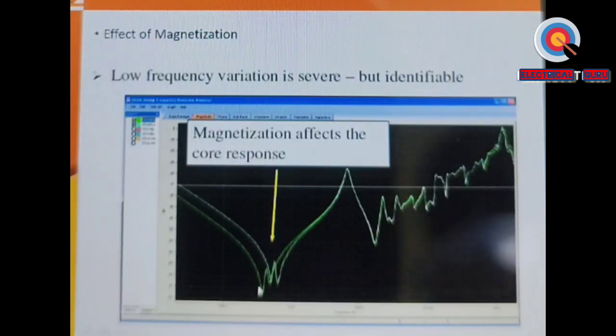We say that up to 10 kilohertz you will see the change in core behavior or magnetization in the core, and this plot is typically explaining that, this green line and blue line. It shows that previously the core had residual magnetism, which is plotted by the blue line, and you can very clearly observe that after 100 kilohertz, or even from 50-60 kilohertz, this plot is almost merged. So up to 10 to 20 kilohertz, this is predominantly reflecting the core area, and you can see here the behavior of the core, residual magnetism versus an unmagnetized core.